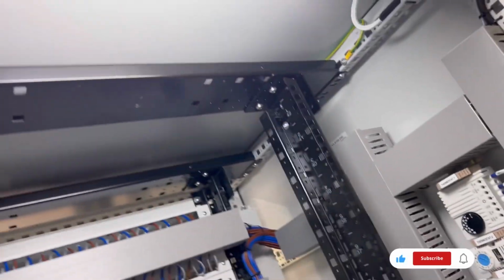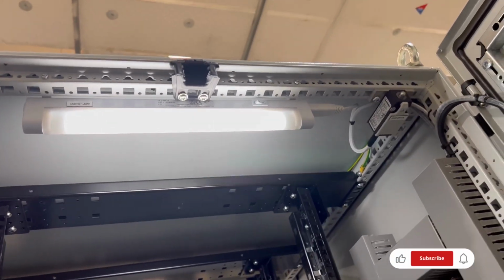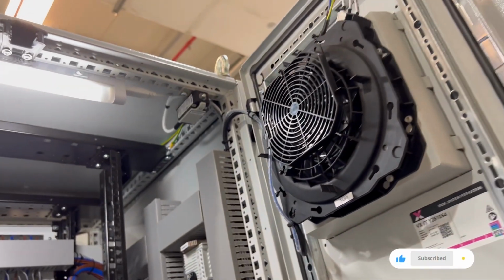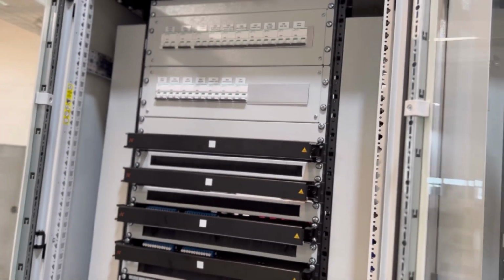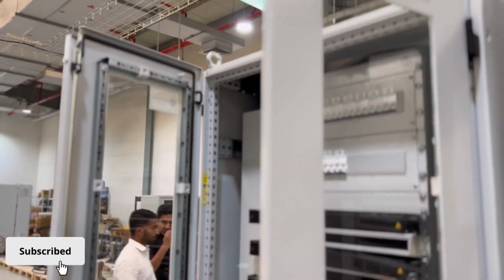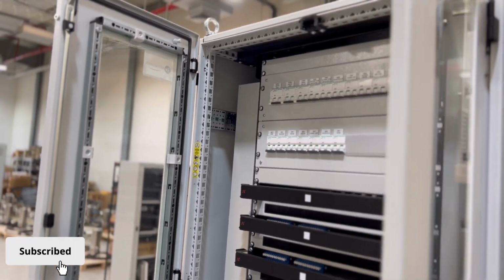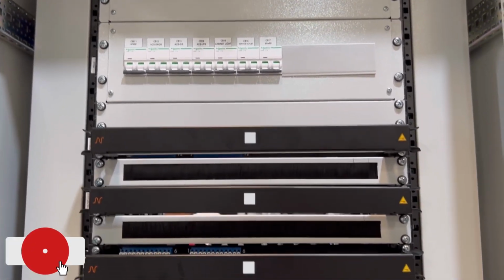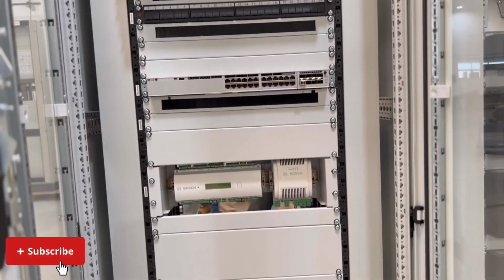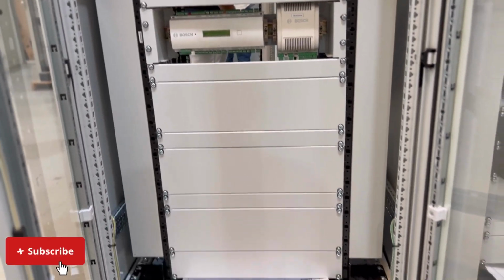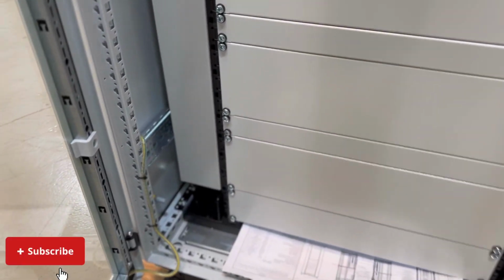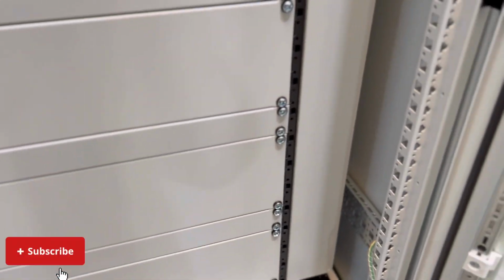As you can see in the video that I captured, I will check all the devices, fans, lights, breaker. Sometimes for the breaker, for example, there is a minor mistake: 25 amps as per drawing, and then you install 50 amps. So you need clarification from the engineering why it's happening, because the drawing is showing only 25 amps. And then the installation during your inspections is 50 amperes. So that's to be verified.